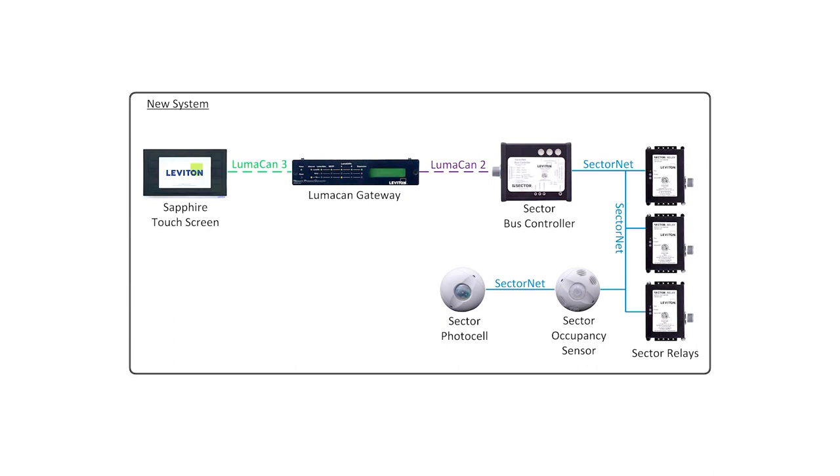Okay, so there are some very unique things here. For example, all I have on the Luminet line is the 4200 — there isn't anything else. So what I'm going to be doing is converting that Luminet line to a LumaCAN line, changing the gateway to become, instead of a Luminet to LumaCAN gateway, a LumaCAN 3 to LumaCAN 2 gateway. That's going to allow me to put in a Sapphire touchscreen in the same place as a 4200. Now, if there were other things on this network, this wouldn't work, so this is really a specialized case, but I did want to share the application with you specifically.